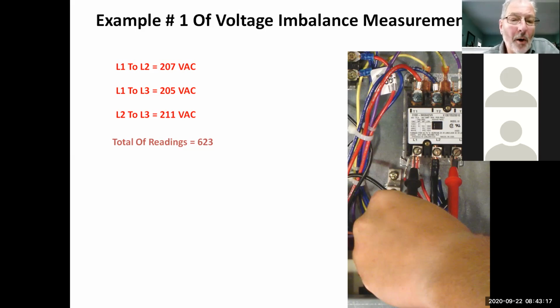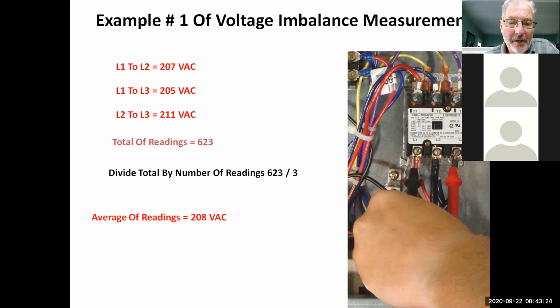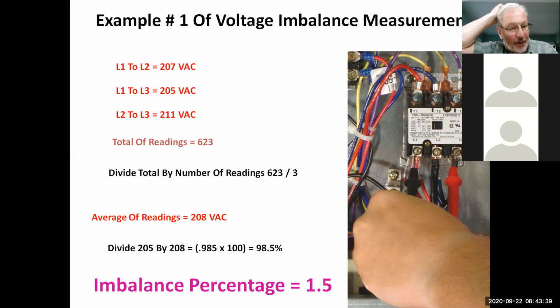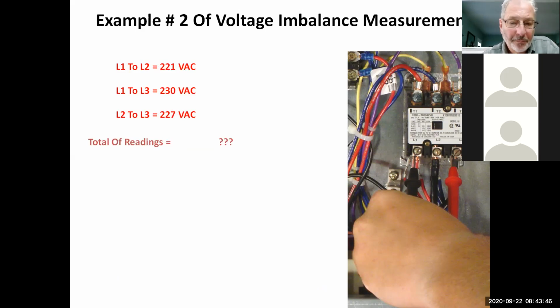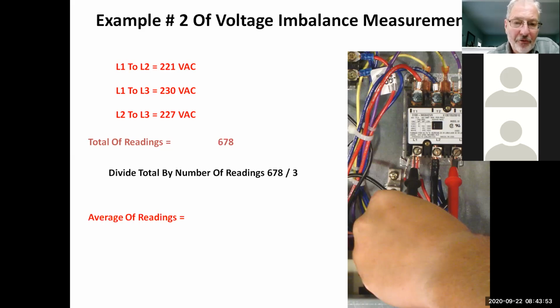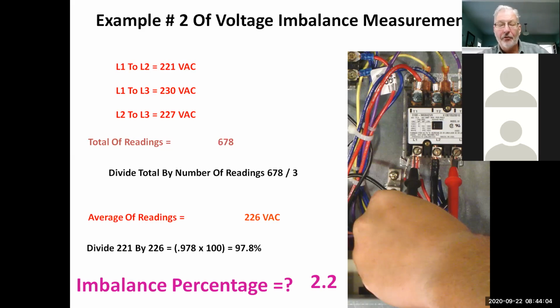So basically what we do is we take our voltages, we average them out, divide them by 3, take the farthest deviation. In this case, we got an average of 208, and the farthest deviation is 205. We have an imbalance percentage of 1.5%, which is perfectly acceptable. Okay. In this case, we add voltages up. We divide by 3, take our average, and the farthest deviation. So 226 divided by 221. And my imbalance is 2.2%. This is not acceptable. This has to be corrected.